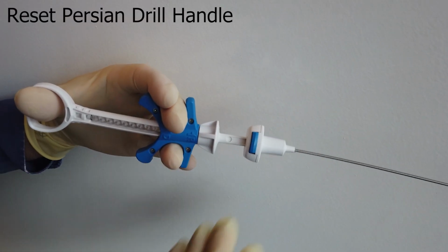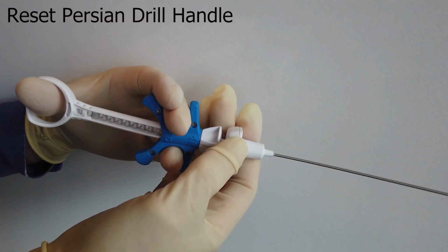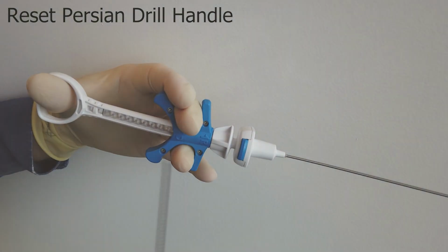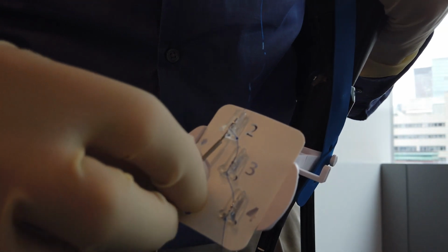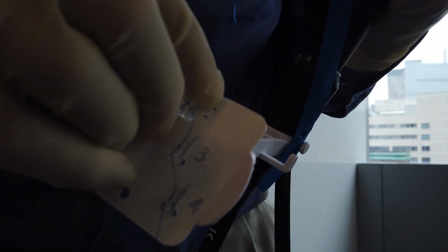After first resetting the handle, the blue button is pulled back to its original position. This pushes the tip out from the end of the delivery shaft, which allows it to be loaded with the next tack. The delivery device is then inserted into the plastic tack loading sheath on the card and pushed until the tip clicks into the tack.